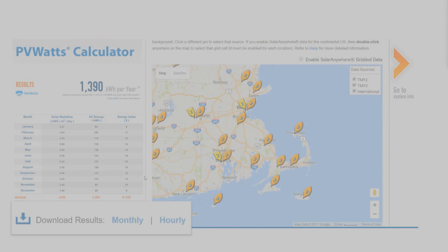You might be asking yourself at this point, well, where do I go and get design temperatures? How hot does it get up on a rooftop? How hot are my modules and my equipment up there going to get? And actually, for your design work, you're supposed to use the ASHRAE database, but that ASHRAE database won't convert from the ambient temperature to that rooftop surface. If you want to get an idea of what the module temperature is, we can go back into PV Watts, which we've explored in previous classes.